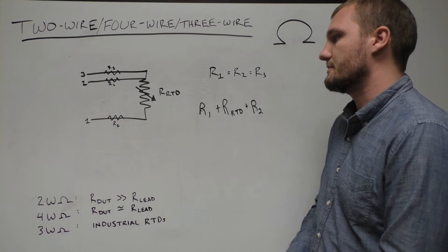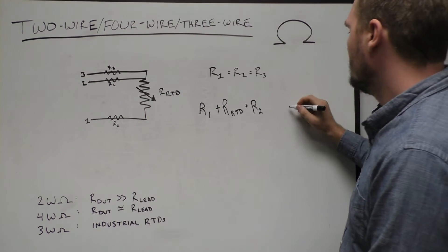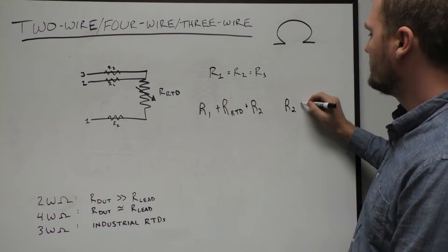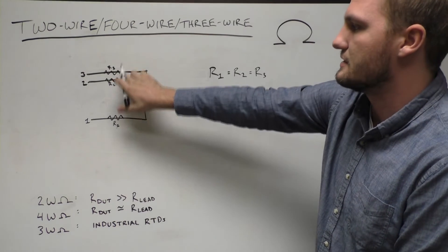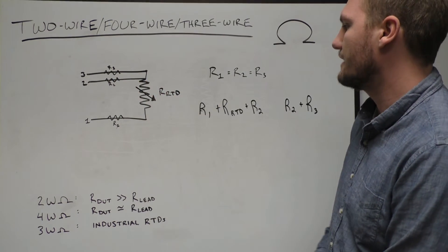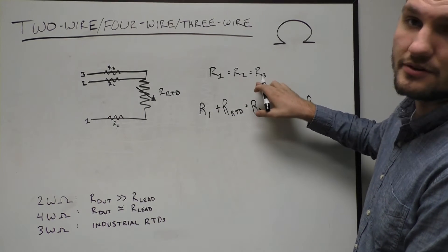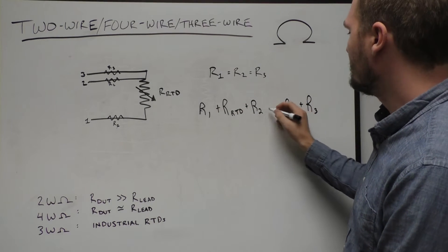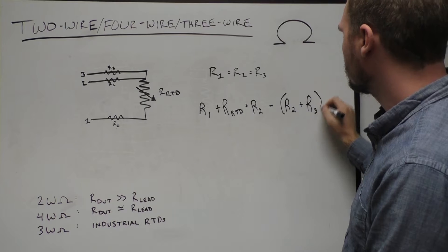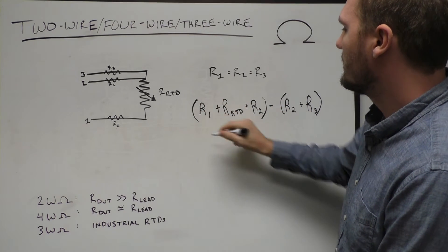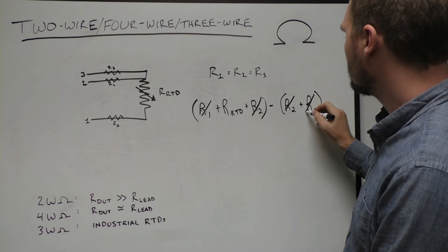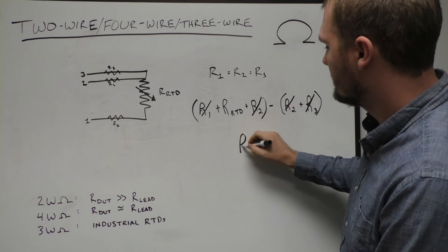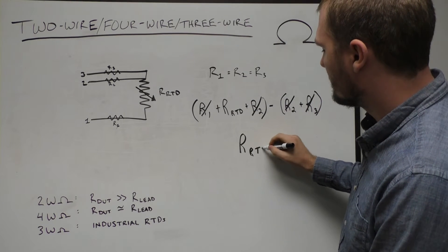So you have the lead resistance of this wire and this wire and the RTD. Then you make a second two-wire measurement between points 2 and 3, which gives you R2 plus R3, so the lead resistance of both of these wires. And now, because R1, R2, and R3 are all equivalent, you can subtract these two measurements and cancel out R1 and R2 and R2 and R3, leaving you with just the resistance of the RTD.